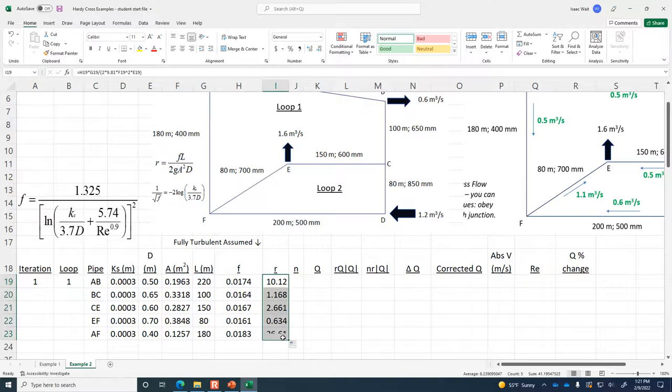For the first pipe, the R value is 10.12. Pipes that are short will have a relatively lower resistance — look at pipe EF: it's a short pipe with a big diameter, so plenty of water can go through without much head loss. In contrast, AF is our smallest diameter pipe and that's what drives up the flow resistance through pipe AF.